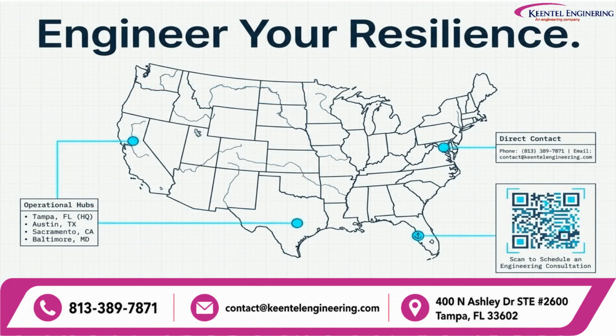Transformer protection is ultimately about resilience. A resilient power system does not depend on a single relay, a single calculation, or a single protection function. It depends on an engineered system where measurements are accurate, protection logic is correctly designed, protection zones are properly coordinated, trip circuits are reliable, and commissioning proves that the complete system works as intended. From utility-scale generation to substations and battery energy storage systems, the same principle applies.